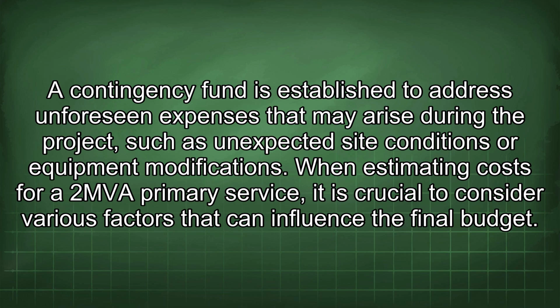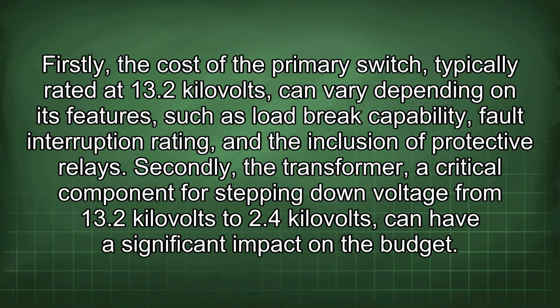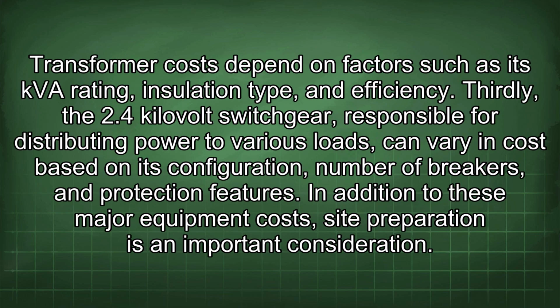When estimating costs for a 2 MVA primary service, it is crucial to consider various factors that can influence the final budget. Firstly, the cost of the primary switch, typically rated at 13.2 kilovolts, can vary depending on its features, such as load break capability, fault interruption rating, and the inclusion of protective relays. Secondly, the transformer, a critical component for stepping down voltage from 13.2 kilovolts to 2.4 kilovolts, can have a significant impact on the budget. Transformer costs depend on factors such as its kVA rating, insulation type, and efficiency.